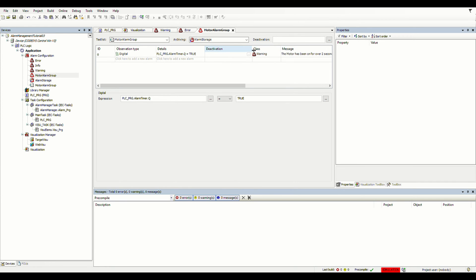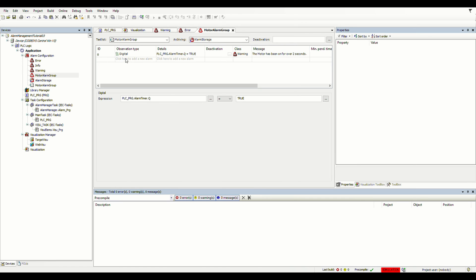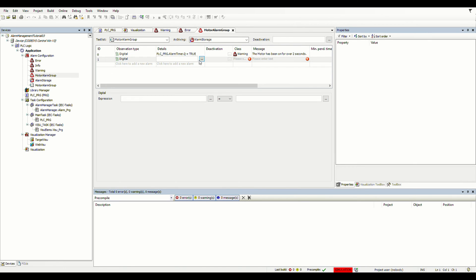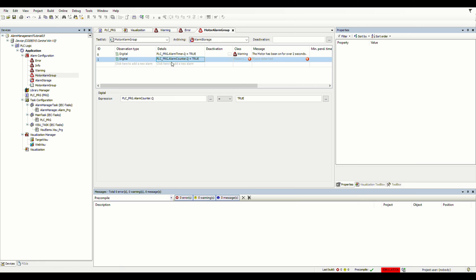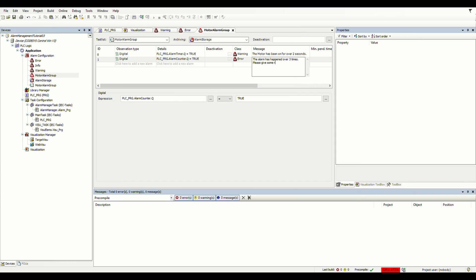When this alarm happens, we will receive a warning with the configured message, shown with an orange background and black font. The second type of alarm is regarding the done bit of the counter — when alarm_counter.Q equals true, we will have the alarm and the class for this alarm will be error, so the background will be red and the font will be white. We can also have some text shown to the operator when this kind of alarm happens. Here we have the definition of both alarms and their properties.